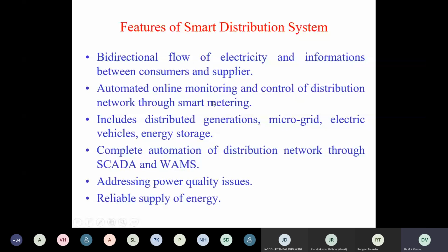At the substation, there must be some control and application software, and based on running this software, decisions like billing, control of overcurrent, and detection of theft are made. All these are issues related to the distribution network: detection of theft, and protection against overcurrent. Unbalancing is one of the main issues in distribution networks: how to balance load. So all these have to be done based on the measured quantities from smart meters. All decisions like load balancing, theft detection and removal, and overcurrent protection of feeders are to be done based on measured quantities. And so there should be bidirectional flow of electricity as well as information from consumers.